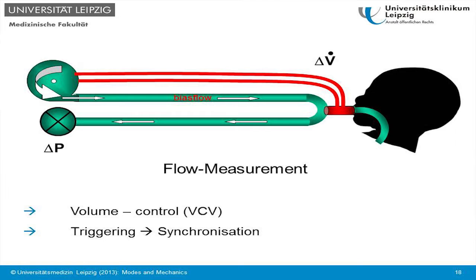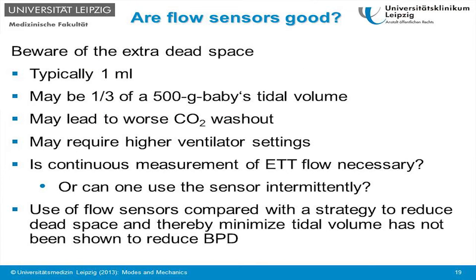If we want more sophisticated ventilation modes and more information from the patient, we need additional sensors, many devices of a flow sensor being inserted here between the ventilator circuit and the endotracheal tube. So we can measure the flow, we can integrate the flow to volume, and we can offer volume-controlled ventilation and synchronization with the patient's efforts by doing this. However, we have always to be aware that there is no study showing that the use of flow sensors actually has benefits for the patients.